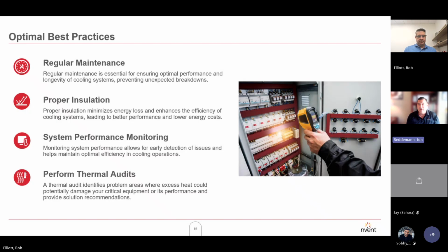The other thing that is extremely critical is proper sizing. In my eyes, and we've been doing this for a couple of days now, you can't oversize a fan. Unless we have contaminants in the air, we don't want to push more air through there than we really need to. But if we have free air available, let's push as much air through it as we can and keep the enclosure cool. It's always going to be warmer than dew points, so we won't have to worry about it. Air conditioners, let's not oversize those. Heat exchanger, if we have surface area, it doesn't hurt to put a slightly larger heat exchanger on there. Oversizing the air conditioner is absolutely detrimental to the system, not only the air conditioner but also the internal components. And then, best practice, let's perform some thermal audits on those critical systems and keep them up and running.